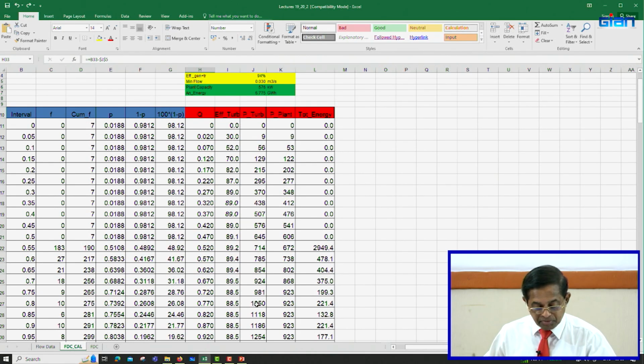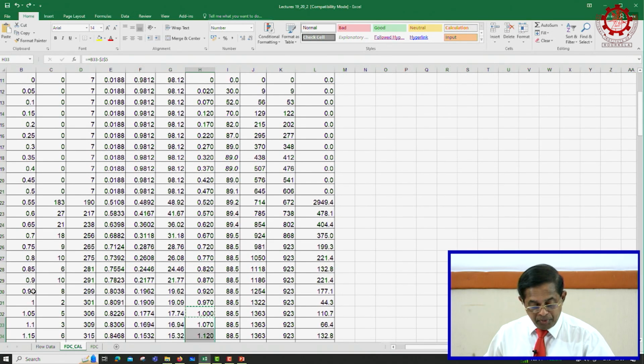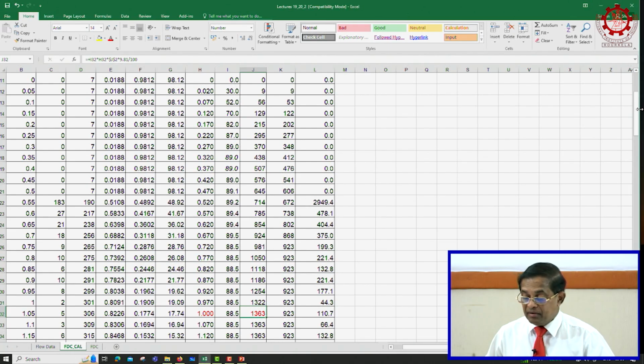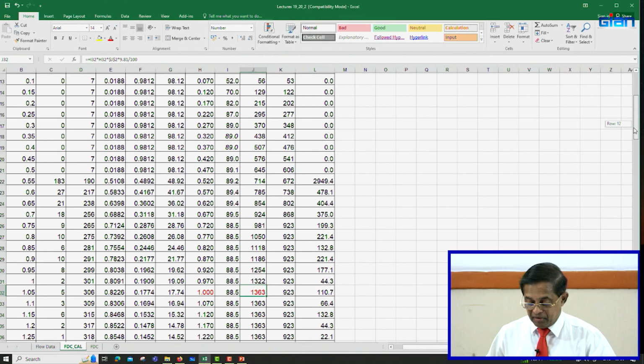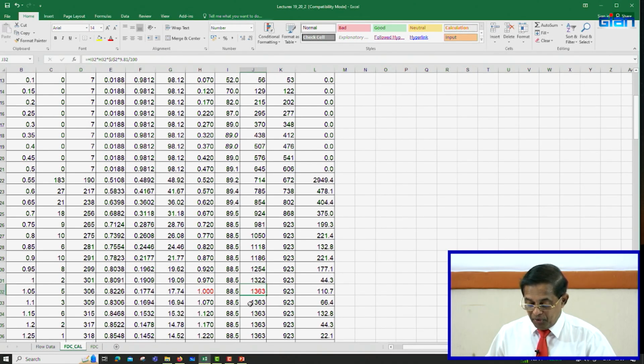capacity. So, here it is corresponding to 1 cubic meters per second flow. Sorry, I made a mistake earlier, it should be 1363, right. 1363 is the plant capacity corresponding to 1 cubic meters per second flow rate, right. Turbine capacity is 1363, right. We are looking at the P turbine here. So, you can see now, we cannot have beyond that. That is why I have frozen the value, even though the flow is increasing, 1.07, 1.12 etc., I have frozen it to 1363 beyond that.